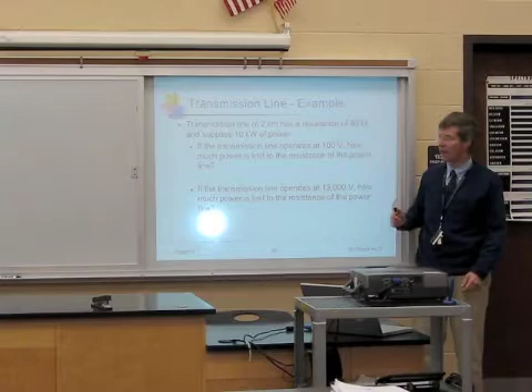But here's an example that illustrates the problem for why you want high voltage power lines. Let's say you have a line operating at 100 volts, with a 40 ohm power line. You have a power source, and you're sending it through 40 ohms, and then you want to dissipate some power at the load. Let's say this load is operating at 100 volts, and we want to deliver 10 kilowatts of power to it.